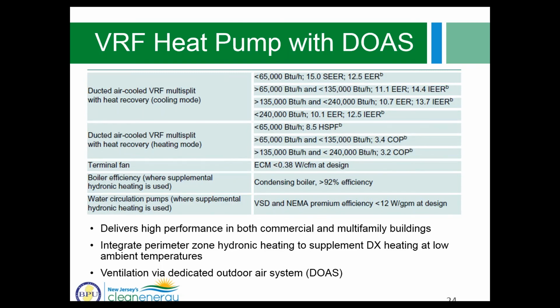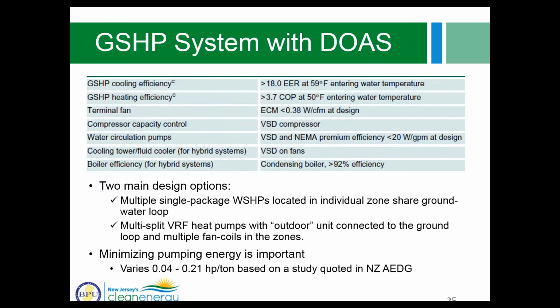Another option that we actually see pretty often on projects going through P4P is VRF heat pumps with dedicated outdoor air system. So there again, opportunity for savings involves specifying units with high heating and cooling efficiency, using backup heating through condensing boiler in the perimeter zones, reducing pump energy to no greater than 12 watt per GPM in design conditions, and using dedicated outdoor air system in conjunction with VRF heat pumps that provide heating and cooling to spaces.